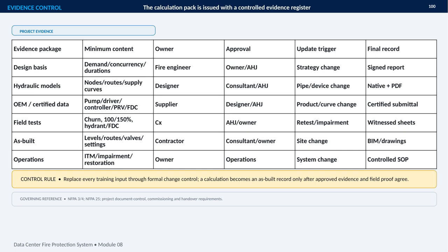Certified manufacturer data supports the pumps, drivers, controllers, pressure-reducing valves, and fire department connections. Field tests provide proof through Churn, 100 and 150% flow testing, and Hydrant or FDC testing. As-built records confirm actual levels, routes, valve positions, and settings, while operations documentation controls inspection, testing, maintenance, impairment, and restoration procedures. The central rule is approved evidence and field proof must agree before a calculation becomes an as-built record. Any training input must be replaced through formal change control. This process is governed by NFPA 3 and 4, NFPA 25, and the project's document control, commissioning, and handover requirements.